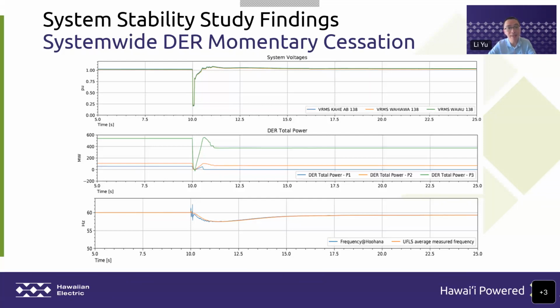That's why in the middle figure you can see the DER generation, after it reached the top, starts to reduce in that green curve. That basically means DER gets shed in the underfrequency load shedding. Because of the underfrequency load shedding and the remaining thermal generation ramping up, the system frequency gets stabilized and then gradually settles close to 60 Hertz.